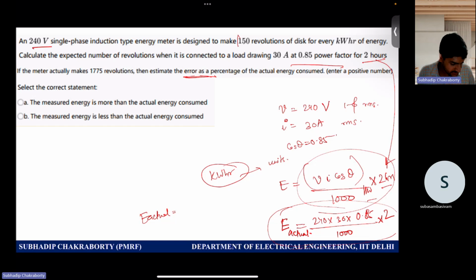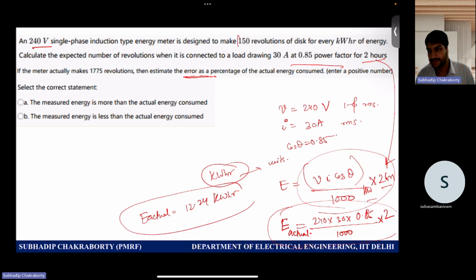Let me just calculate how much it will come: 240 into 30 into 0.85 into 2 divided by 1000. So 12.24 units, or 12.24 kilowatt hour. This is the actual energy that is dissipated and recorded by the instrument, the true value.